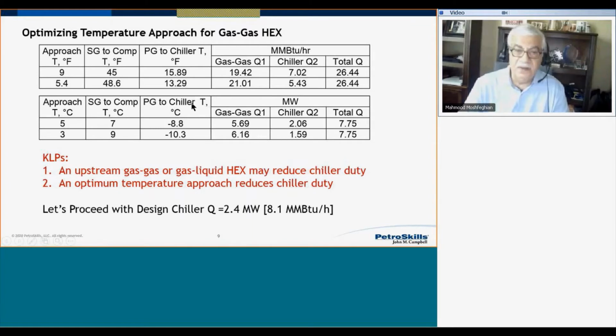The second lower table is the same information in SI units. So the takeaway from this discussion so far is these two key points: an upstream gas-gas exchanger, or sometimes we may also use a gas-liquid exchanger, may reduce the chiller duty. And also an optimal temperature approach reduces chiller duty, and consequently compressor power goes down, which we'll see shortly. So even though the chiller duty is 7 million, I'm going to use the design value of 8.1 million BTU per hour, or 2.4 megawatt for the rest of calculation as we proceed.